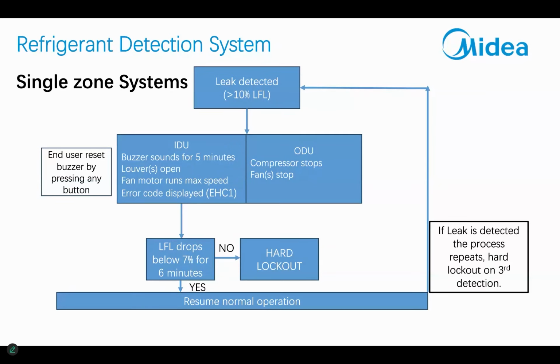If the level comes back down below 7% of the lower flammability limit, the system will restart. If it doesn't, it starts the cycle over again. It'll do that cycle 3 times, and then it will lock out. In order to restart it, the power has to be reset. That's how our leak detection cycle works.